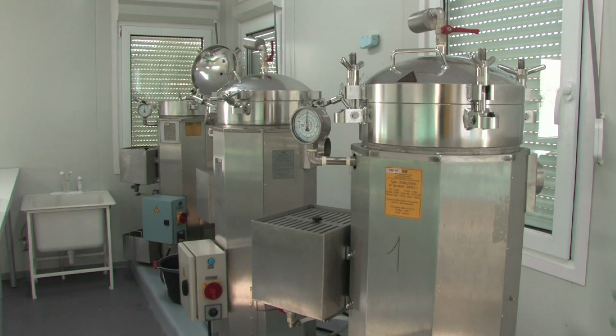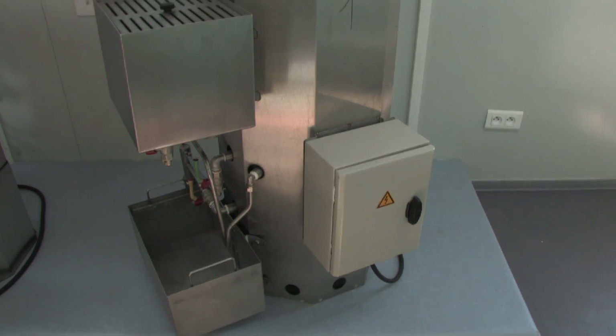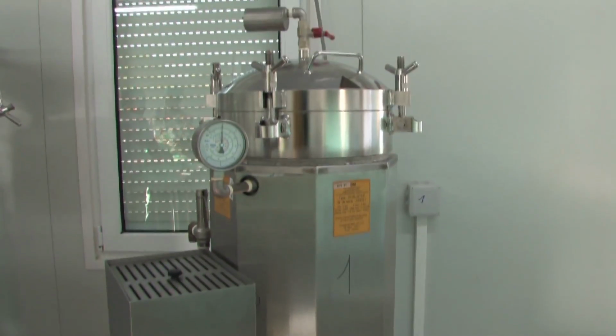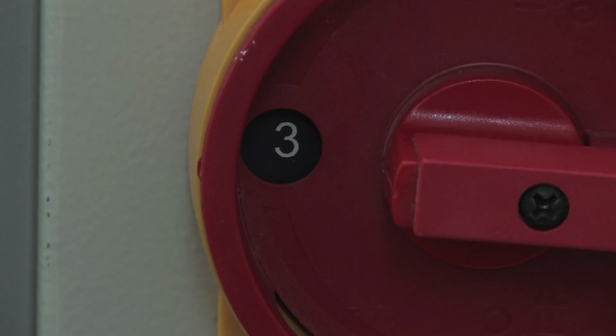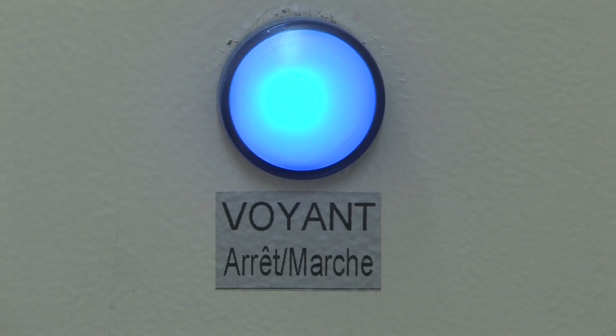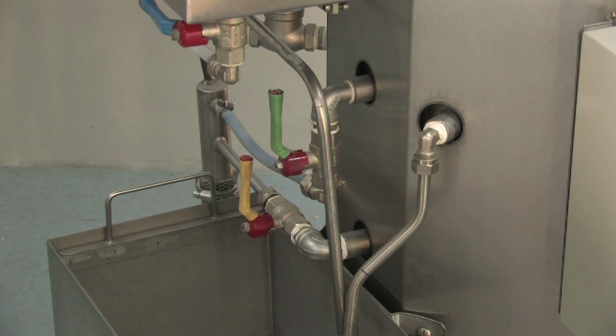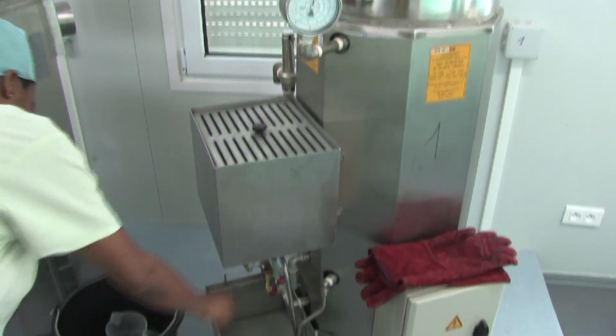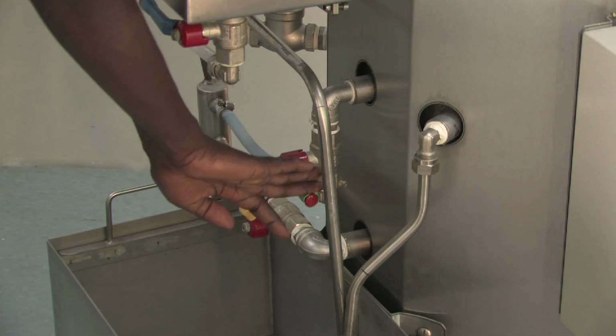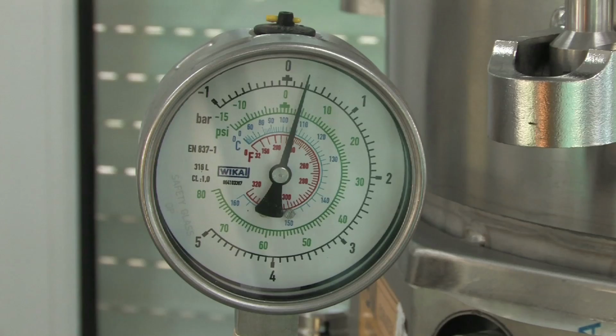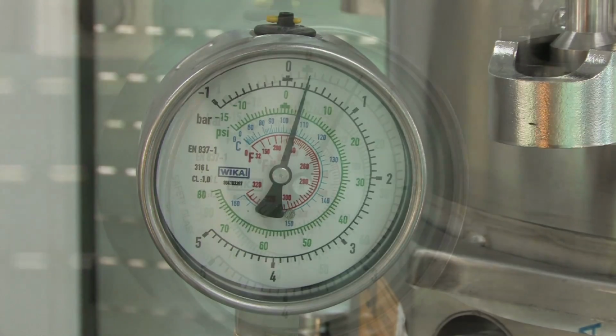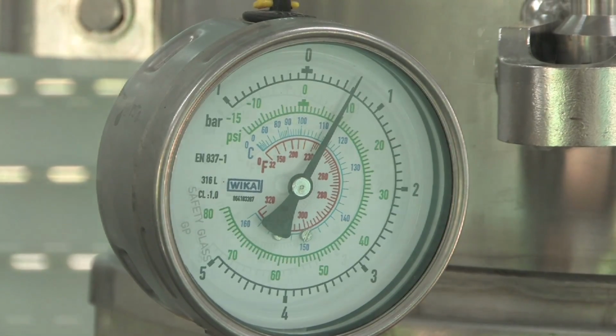3. The autoclave must then be purged, that is, the air in the autoclave chamber must be removed so that steam can take its place. During heating, the water in the tank starts to boil and steam forms. When there's a continuous jet of steam escaping from the pipe at the green valve, close that valve by turning it perpendicular to the pipe. Steam will then build up in the autoclave and the pressure will rise.